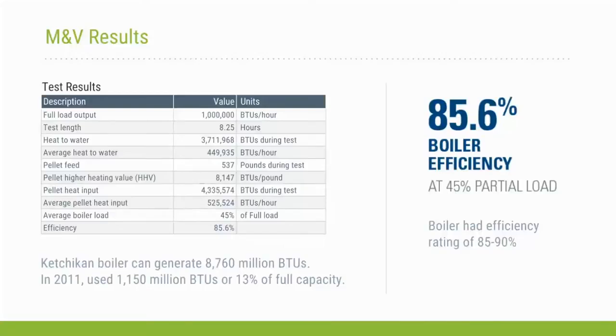Okay, just to overview the testing that we did when the boiler system had been installed for about a year. Claims are made on these pellet systems by vendors, as you always hear, and the boiler efficiency is key to the economics of these systems. And the boiler manufacturer was claiming 85 to 90% efficiency on the system. So I went to the site and set up a system where we would test it for a day. We tested, in essence, the temperature changes coming in and out of the boiler system and the water flow. We also looked at the amount of pellets that had been fed during that period of time.